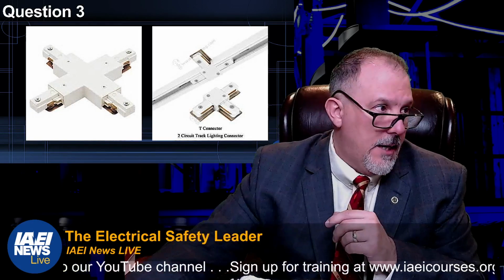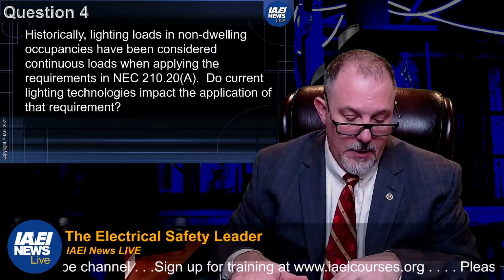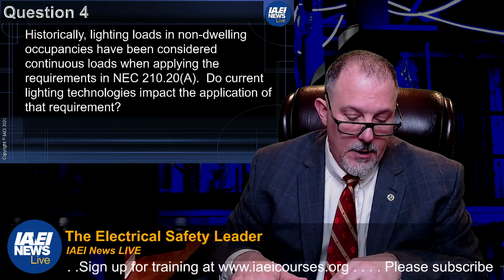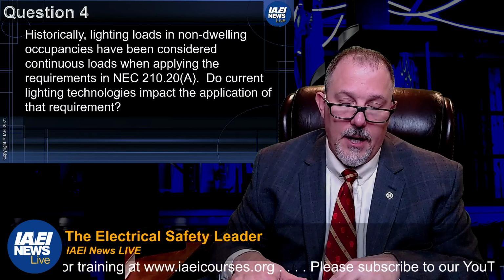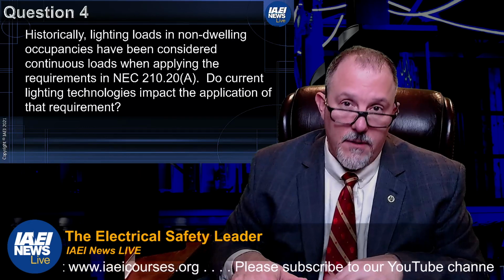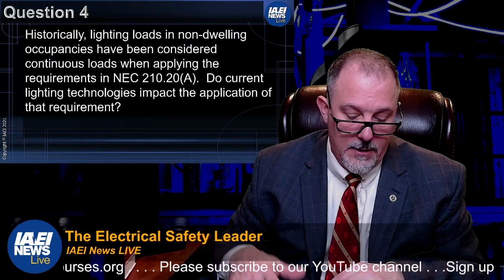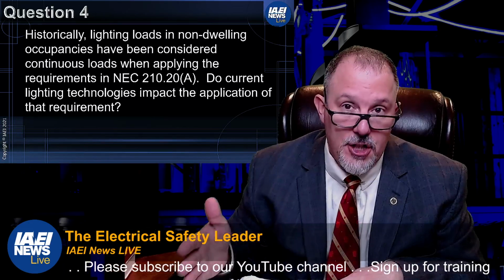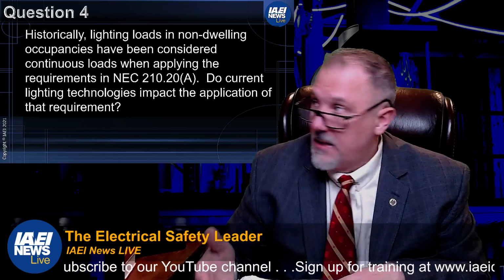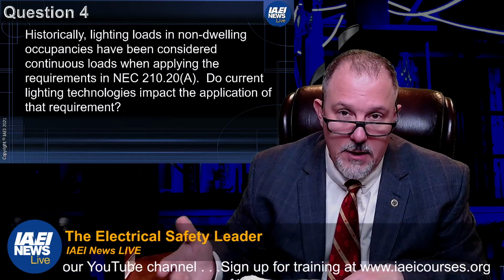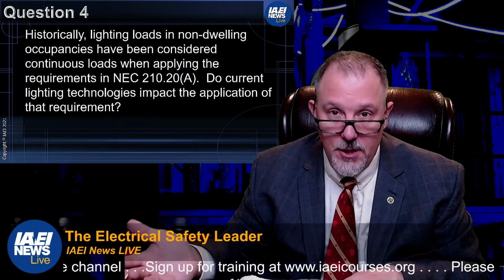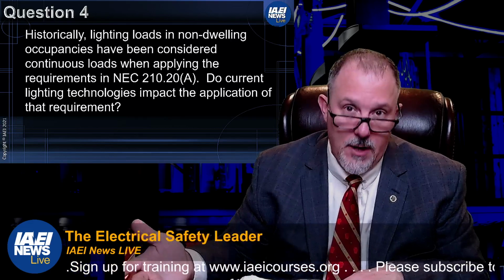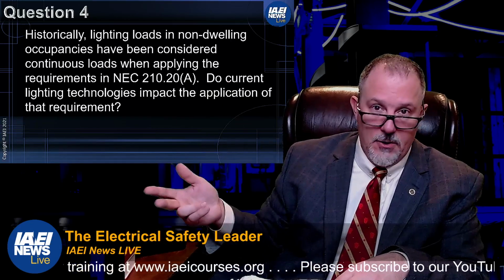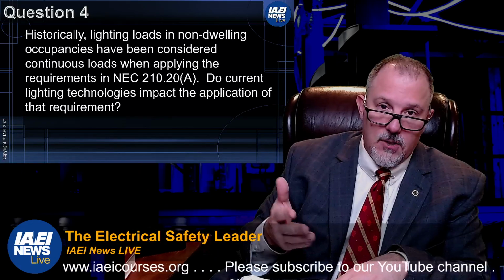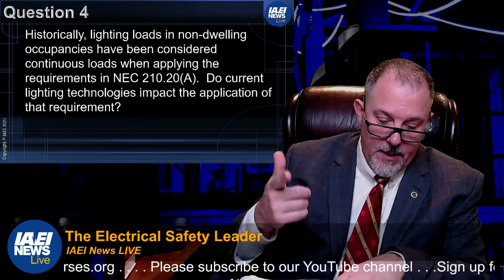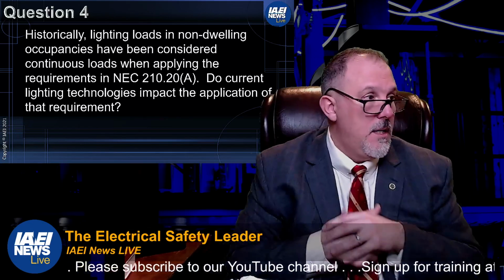It's only able to be achieved through properly applying it and understanding what you're installing, the amount of this track that you're installing, and working that into your calculation. And the AHJ needs to look for it. If they see track lighting and they didn't see anything in the load calculation that addresses it, you've got an issue. You've got to go back and take a look at it. It may or may not impact the size of your service or your feeders, but someone has to account for the footage. So every 2 foot, 150 VA. That's how I'd answer that one.